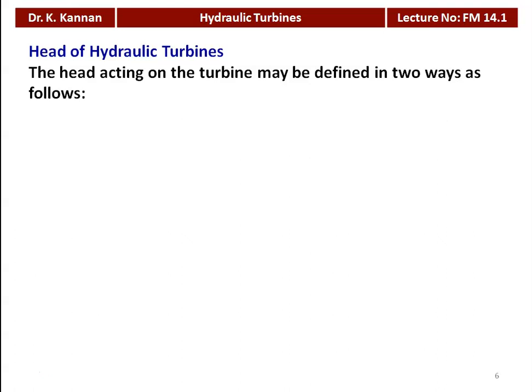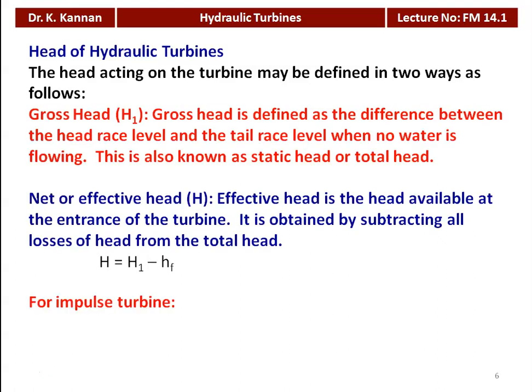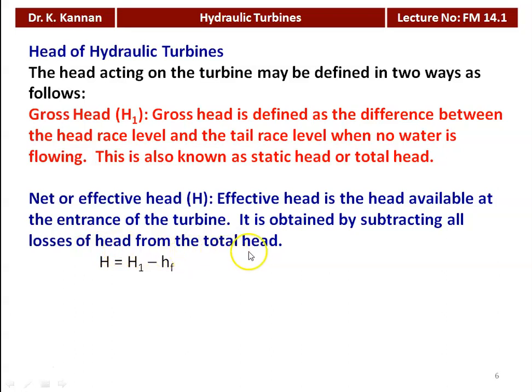The head acting on the turbine may be defined in two ways: gross head and net head. The gross head is the difference between the headrace level and the tailrace level when no water is flowing — also known as static head or total head. The net or effective head is the head available at the entrance of the turbine, obtained by subtracting all frictional losses from the total head. So, net head H = gross head minus head loss due to friction (Hf).